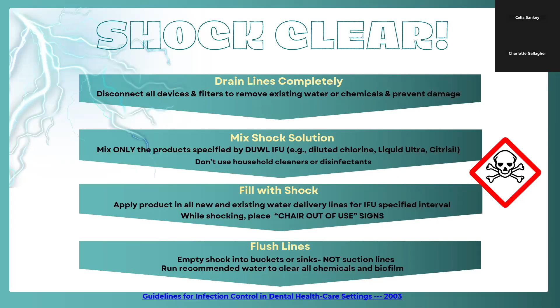If you put treatment products into suction systems, toxic fumes can be developed when they interact with dental materials like amalgam. Make sure to flush the lines thoroughly to clear all the treatment products and the biofilm. The biofilm appears as a gray slimy sludge. The second step is an initial testing to find out the results of your treatment. There are two types of testing you may choose.